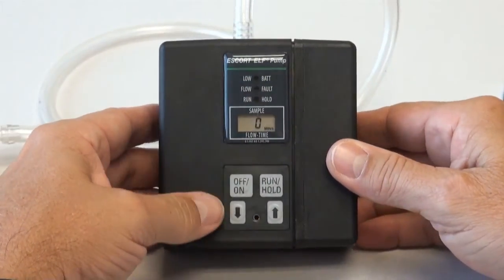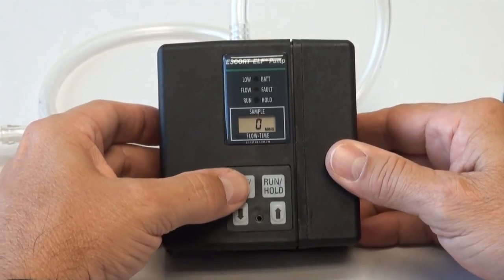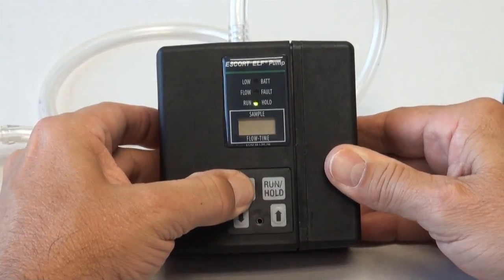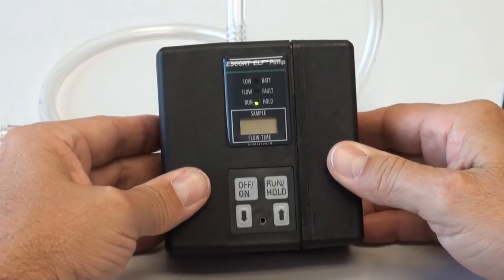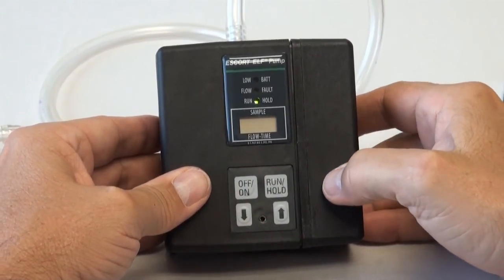When you next turn on the pump, the total operation hours has been reset to zero and is displayed during the initial self-check sequence when the pump is turned on.